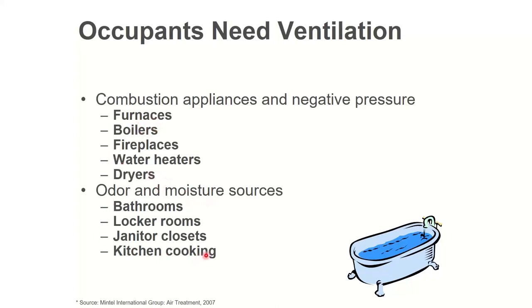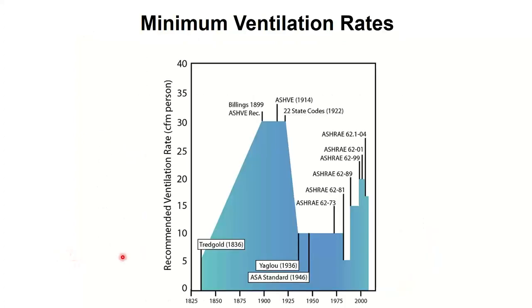There's places that I want to have direct exhaust as well. And I have to make up all of these things with my makeup air. And then unrelated to and in addition to all the makeup air for these, I need fresh air for the occupants. It's a lot of air we're talking about. How much air do I need? Well, if we ignore Wisconsin, 7.5 CFM per person no matter what, and we ignore the city of Chicago, which dictates to you the supply air CFM, and then one third of that comes from outdoors. Everywhere else, so suburbs, Minnesota, Indiana, everywhere else is going to have something that's a derivative of ASHRAE 62, like the International Mechanical Code is a derivative of ASHRAE 62. You look up in a table how much outside air you need.